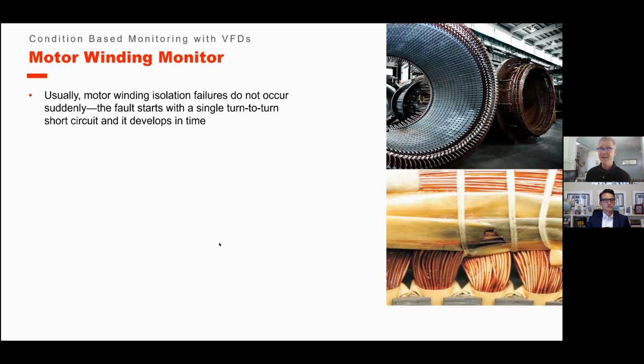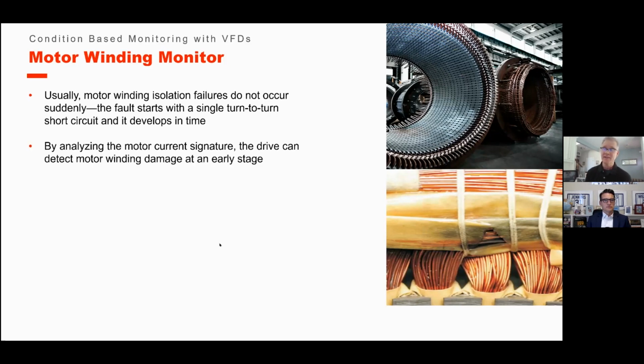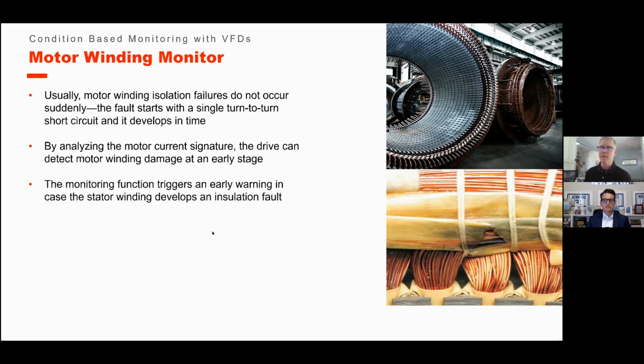So this software helps analyze that motor current signature and detect that motor winding damage at a very early stage. And you have 2 points of testing. You have warning 1, which says, hey, we're starting to degrade, and warning 2, which says it's getting pretty bad. Let's do something before 3 comes on, which is the alarm, and shuts everything down, and we have a complete burnout of the motor. So not only is that expensive in production and time lost, but then you have all the maintenance associated with the motor failure. And that could cause other things to fail, obviously, up the line. So it becomes a major issue.